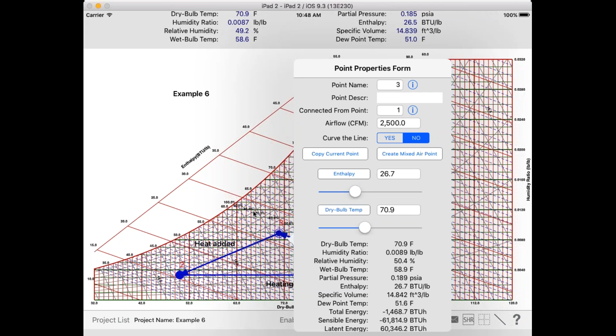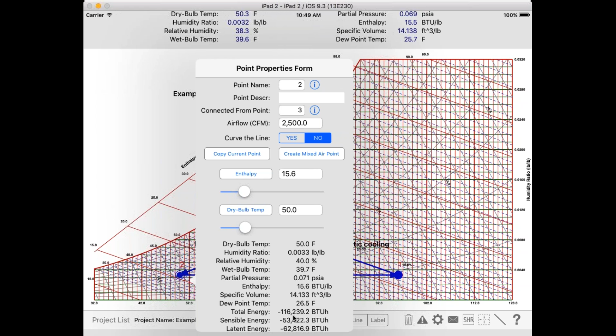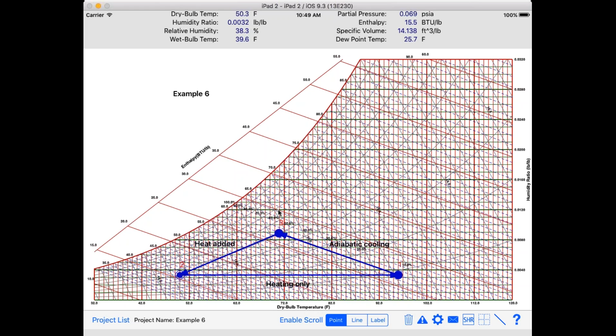Now we also want to find out the heat that was added. If we take the enthalpy here, which was 26.7 BTU per pound, and the enthalpy here, which is 15.6, subtract the two and multiply by 4.5 times our CFM of 2,500, we get about 116,000 of total energy. So as you can see here, we heated and then humidified.